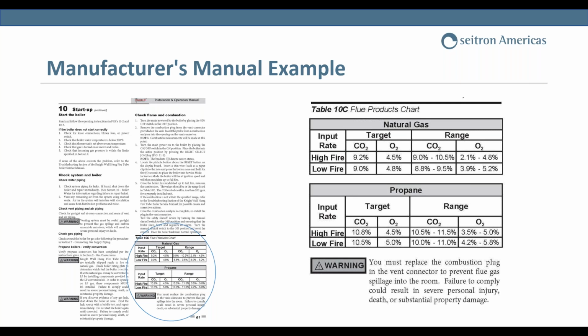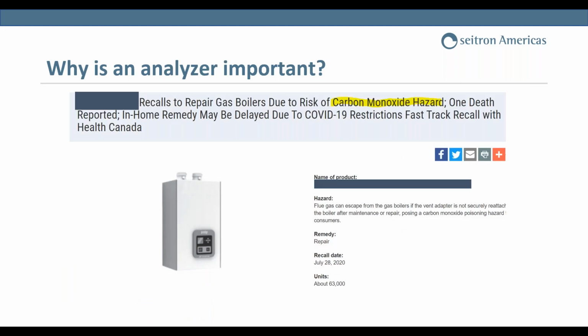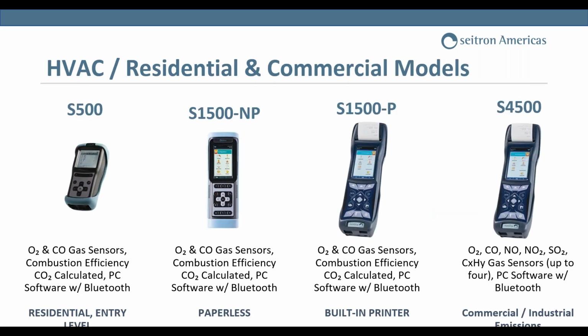Other reasons—this is just, I blurred out who the company is, but this is why this occurs. We had a recall on a particular boiler last year for carbon monoxide hazards. You wouldn't be able to tell, you can't see, smell, or taste CO, so having an analyzer is extremely important to see those kinds of concerns or issues that you can't determine by eye. I tell a lot of my guys during classes, I don't care if the flame is blue, that doesn't mean anything in combustion. So it's just little things like that of why an analyzer is important.